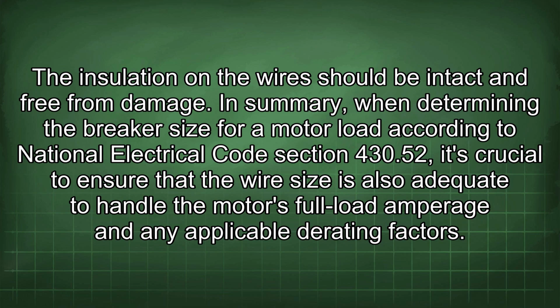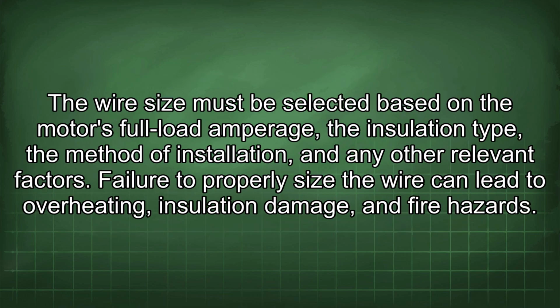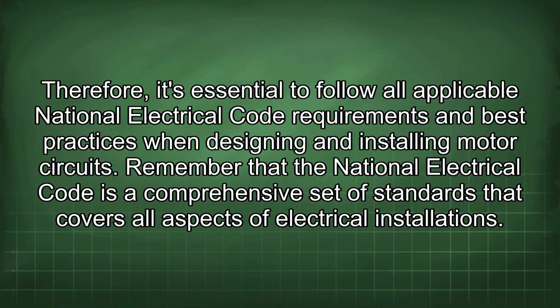In summary, when determining the breaker size for a motor load according to National Electrical Code Section 430.52, it's crucial to ensure that the wire size is also adequate to handle the motor's full load amperage and any applicable derating factors. The wire size must be selected based on the motor's full load amperage, the insulation type, the method of installation, and any other relevant factors. Failure to properly size the wire can lead to overheating, insulation damage, and fire hazards. Therefore, it's essential to follow all applicable National Electrical Code requirements and best practices when designing and installing motor circuits.